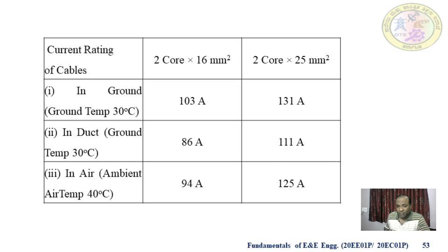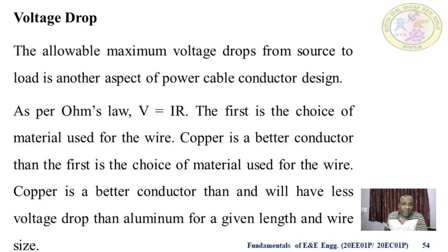And voltage drop. Voltage drop is also important in the case of cabling. The allowable maximum voltage drop from source to load is another aspect of power cable conductor design. As per Ohm's law, V is equal to I R. The first is the choice of material used for the wire. Copper is a better conductor and will have less voltage drop than aluminum for a given length and wire size.